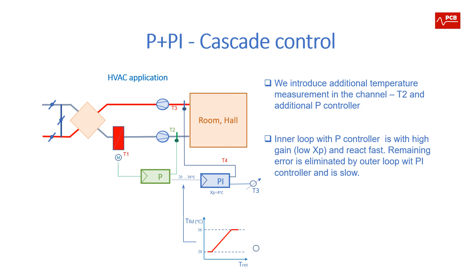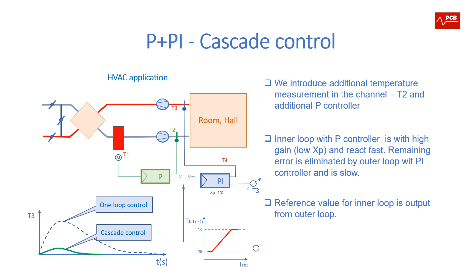So we see the difference in step response when we have only one loop, which uses only one measuring point on a return channel, and in the case where we have a cascade control with an additional measuring point and an additional controller with an additional inner loop. So we see a great difference between these two responses. And in the same way, we can use cascade control in district heating substations, where there are very high deviations and fluctuations of pressures and temperature, and maybe also some other disturbances, and we eliminate them by this cascade control.